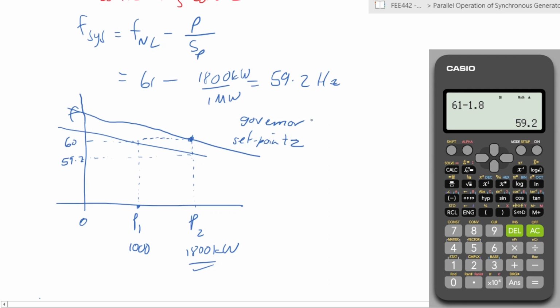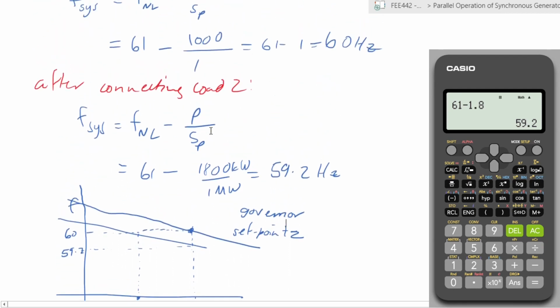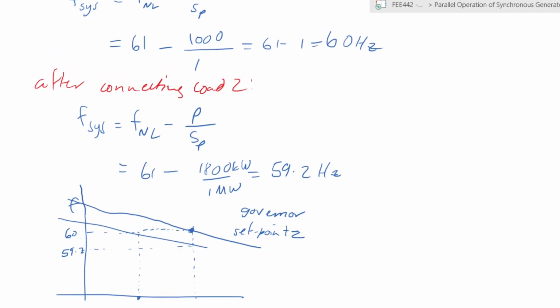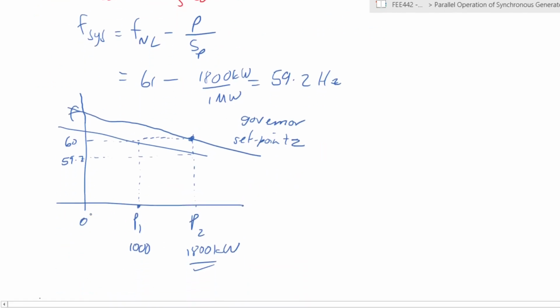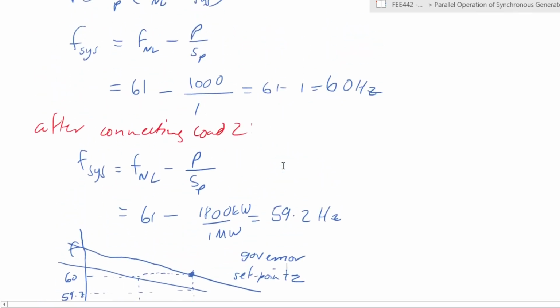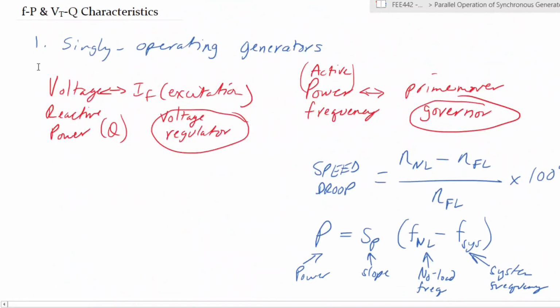So for the short term, when you have a load suddenly increased, it would travel along the machine's characteristic itself. It would not shift in between. For longer term situations where you know that is the load you're going to supply, you would then change the set point to match the situation that you would like to have. Okay, so that's the basic characteristics of machines: voltage and reactive power done by the regulator, active power and frequency done by the governor. So let's look at another situation.